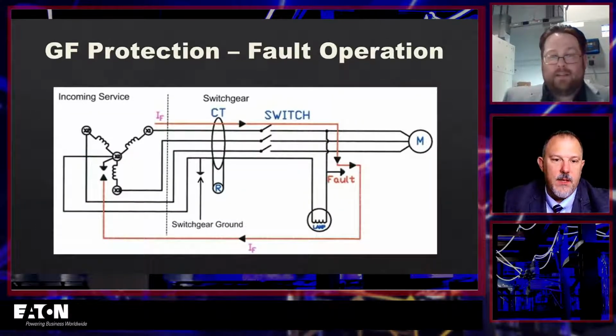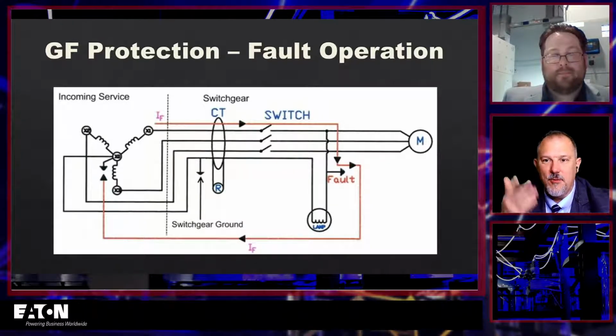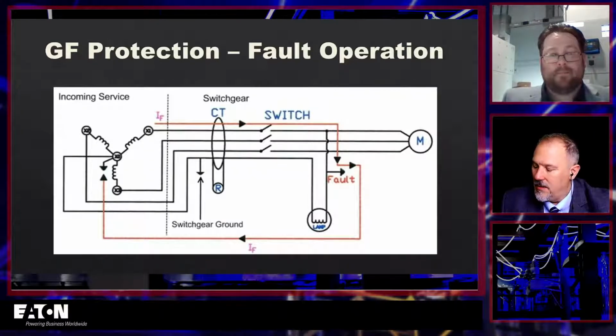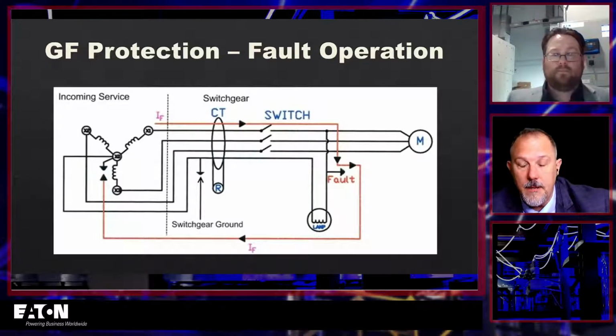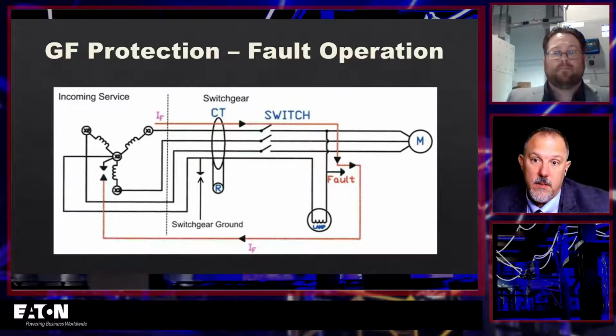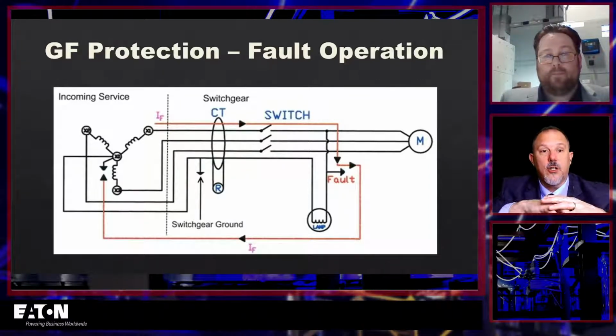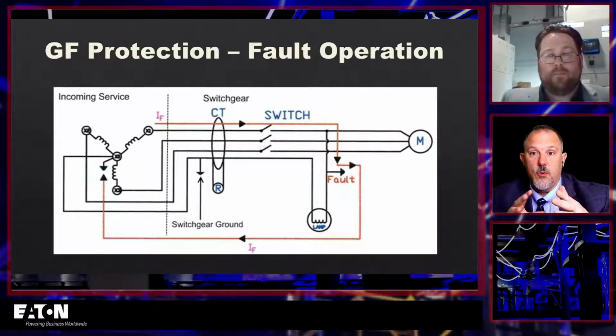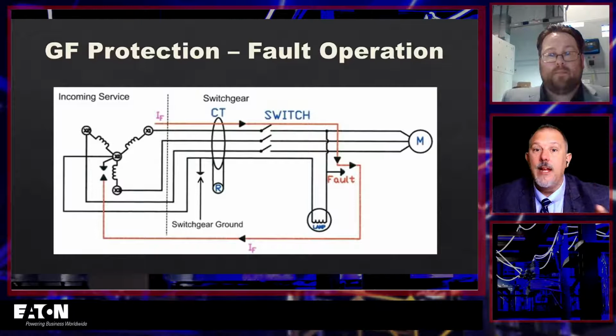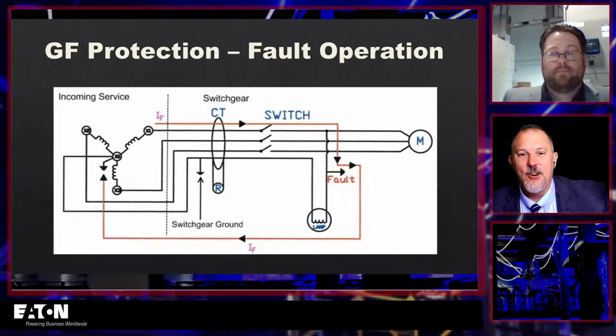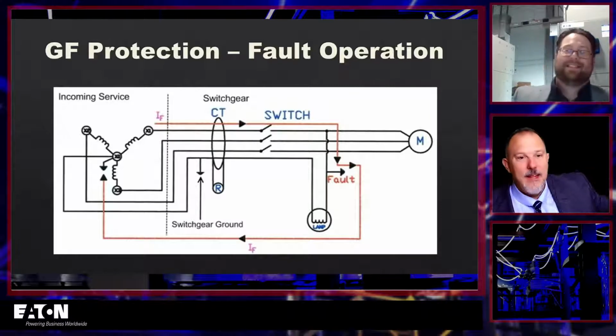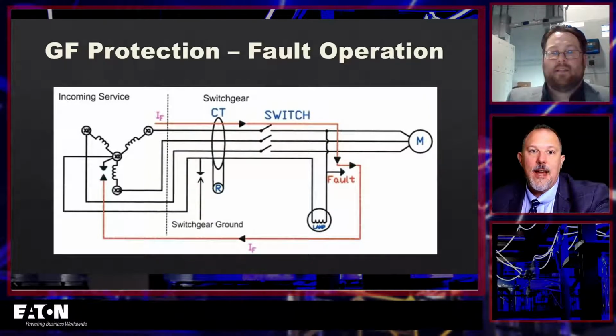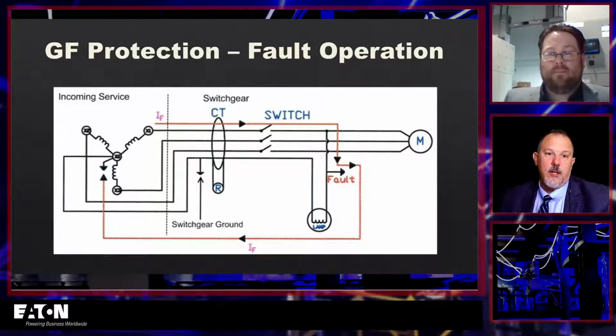So when it does something like this, it's bypassing the zero sequence CT, and you'll notice it goes right into that grounding electrode up through your, what do you call that? The grounding electrode conductor, your GEC, and it's just one big circle. So this would be a separately derived system, because it's all derived from that source. This is the source, and currents will find their way back home, and they circulate. They don't go home to the utility. It's not like they say, "Oh, I'm gonna just go right back to the utility." They go back to these separately derived systems that you've established with that grounding electrode conductor and the grounding electrode, all that good stuff, and your currents will circulate there.